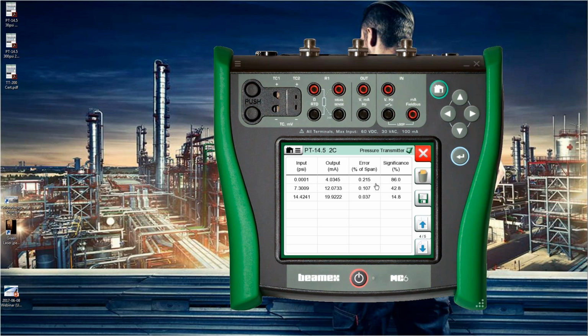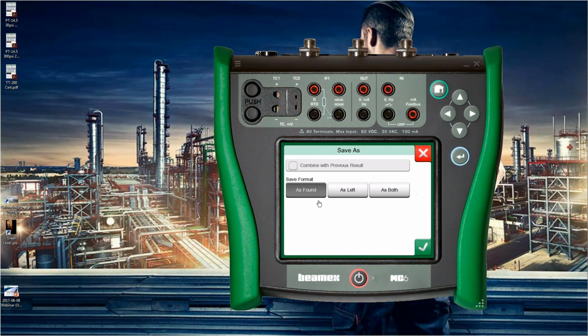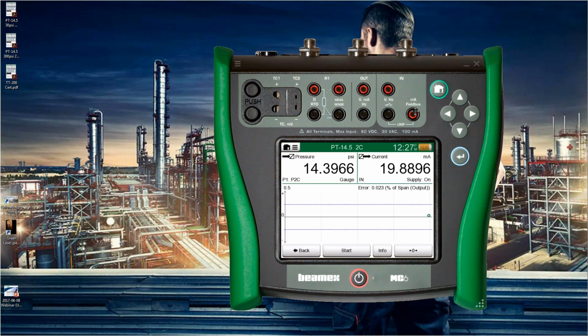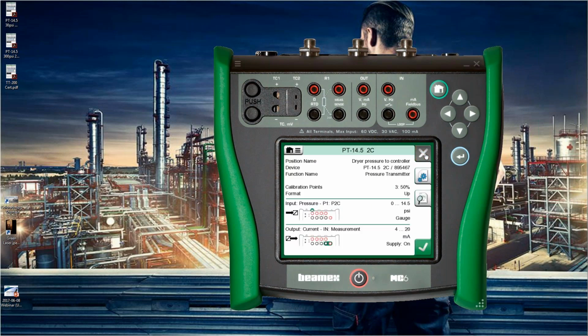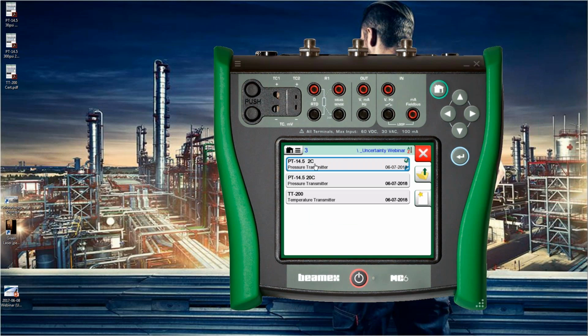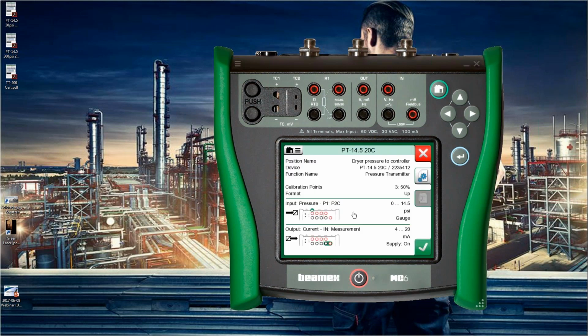I'm not going to take the time to adjust this, and that's not part of this webinar. But if I were to fix this, I would fix the zero first, and then I would adjust the span, and then I'd perform another calibration that would be my as left. So let me save this. I'll save it as found and leave it. Let me go back. Now, this first one I did, I calibrated it with a 30 PSI pressure module. Now, the next one is with a 300 PSI pressure module.